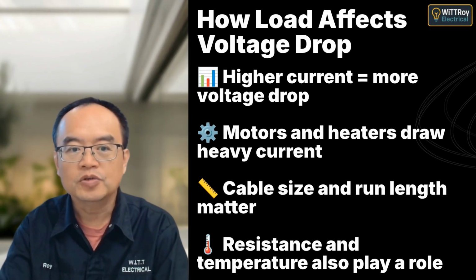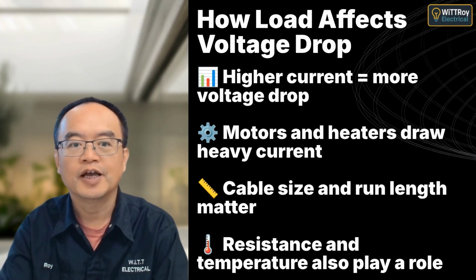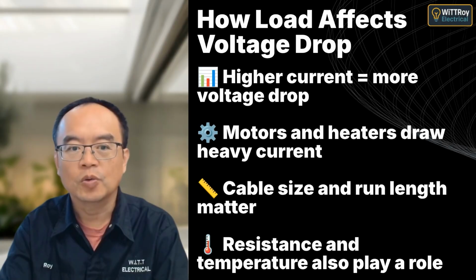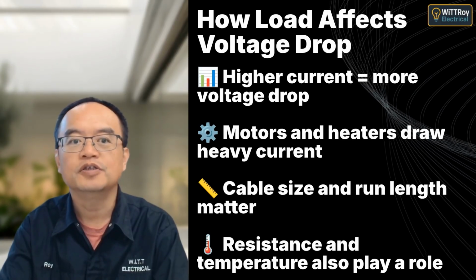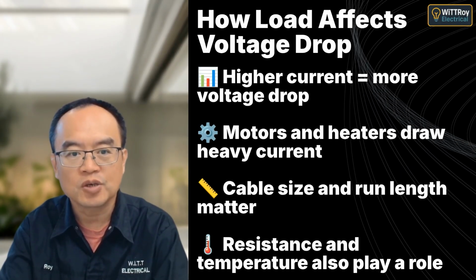The more current you draw, the more voltage you lose across the cable. A bigger load or a longer run will increase the drop. That's why load size must always be considered in voltage drop calculations.